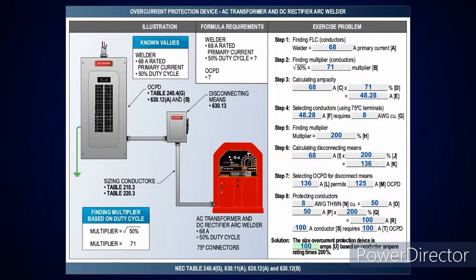I'll say this: I have my reasons why I think there's no outlet, and I give them reasons based on what the code says. When it first started, they were arguing with me, telling me it was at the disconnecting means on the load side, and I said no, it isn't. I said that's a device. Well, they took about 3-4 hours, and then they came back and said it was at the equipment, and I went over that and explained why it couldn't be.